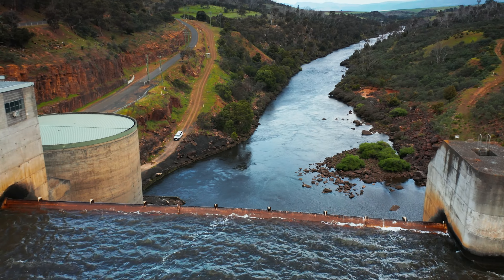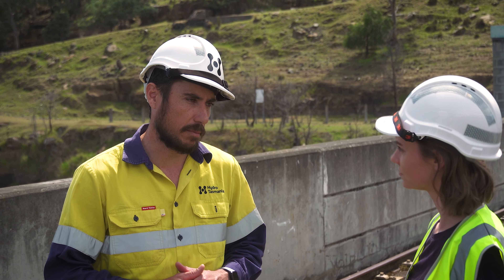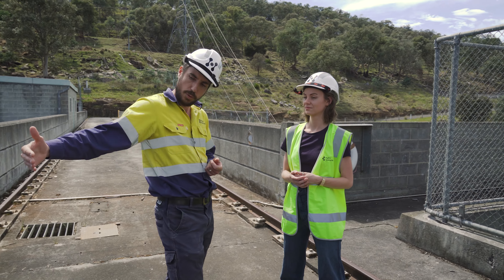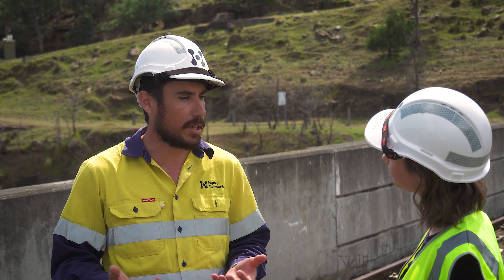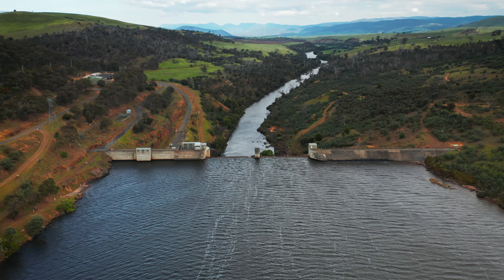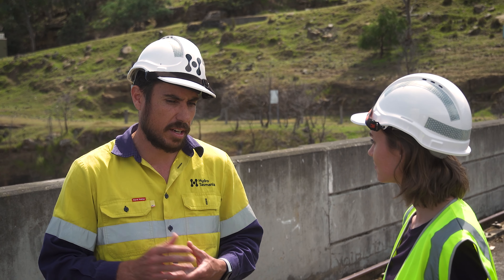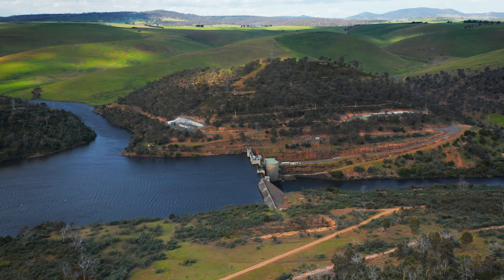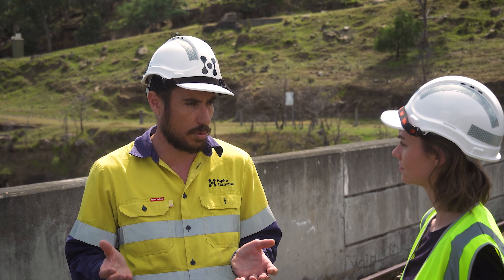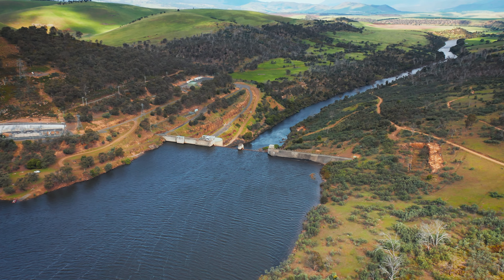So it's a big mass of water and you're essentially channelling it through a smaller turbine in order to produce the energy — that's right. You can hear that rush of water now. Effectively what we're hearing is around 175 cubic metres of water per second going through the intake down into the power station. If you think of a cubic metre of water — a metre by metre cubed — 175,000 of those per second going through. This is quite a small power station compared to the others; it adds around just under 2% to the overall for the state, but it's an important one in the run of the river. There are 10 power stations in the Derwent section, with that cascade effect using the water from the top end down through each station to the last one here at Meadowbank.